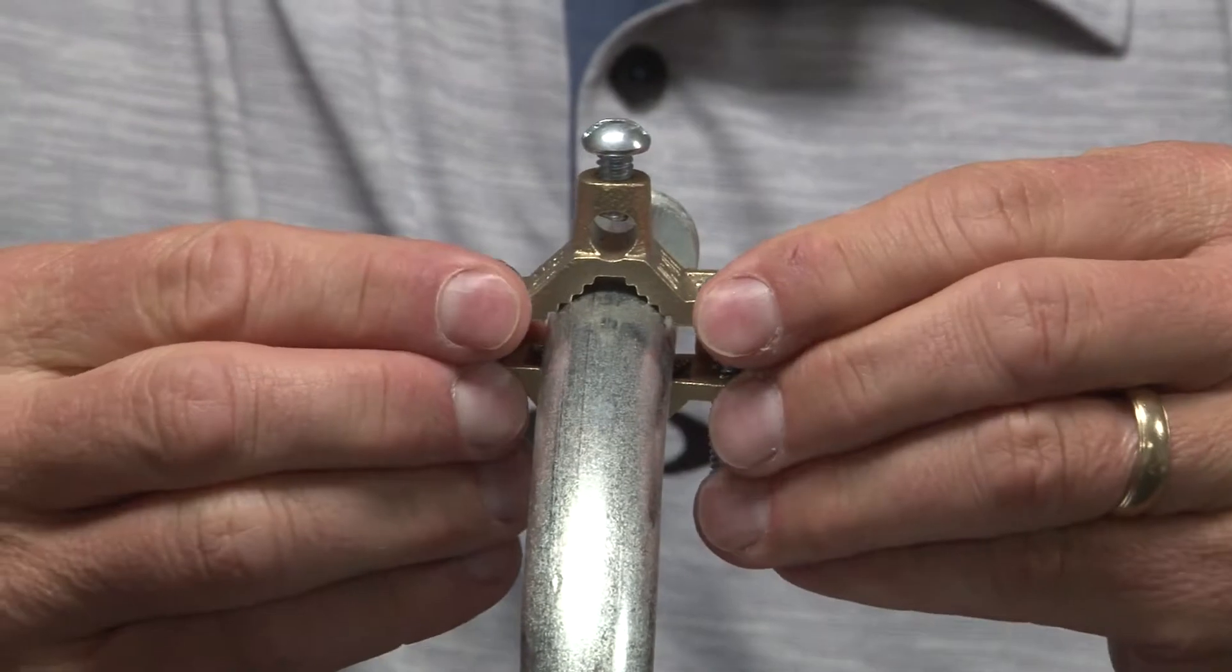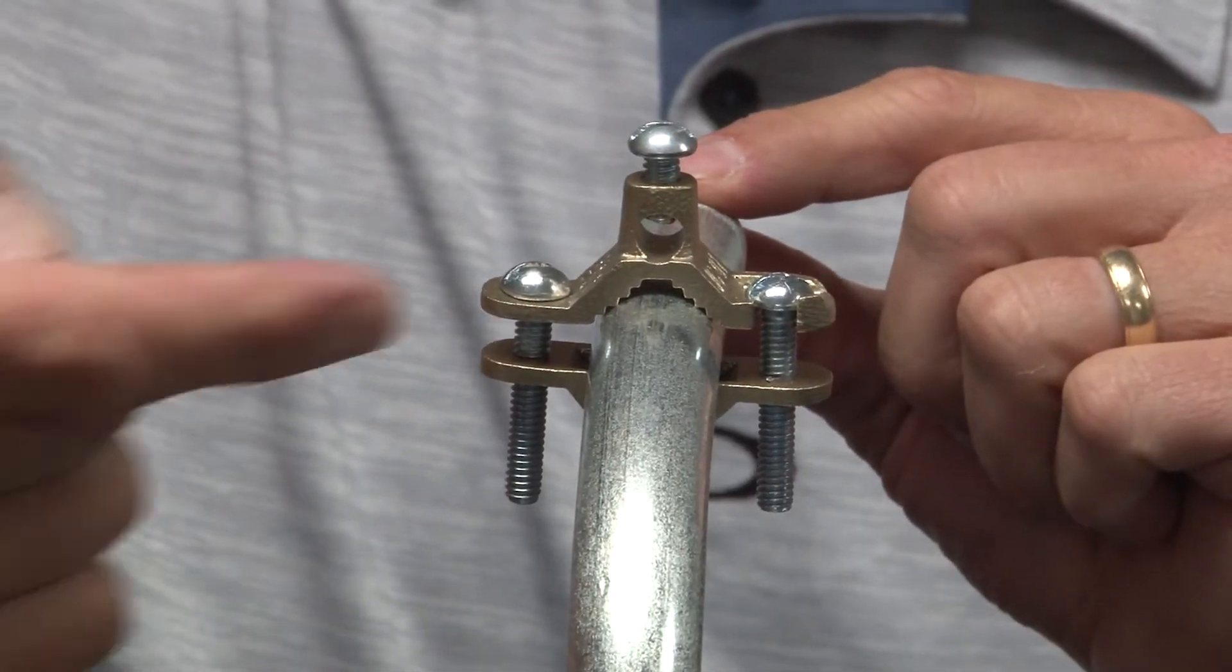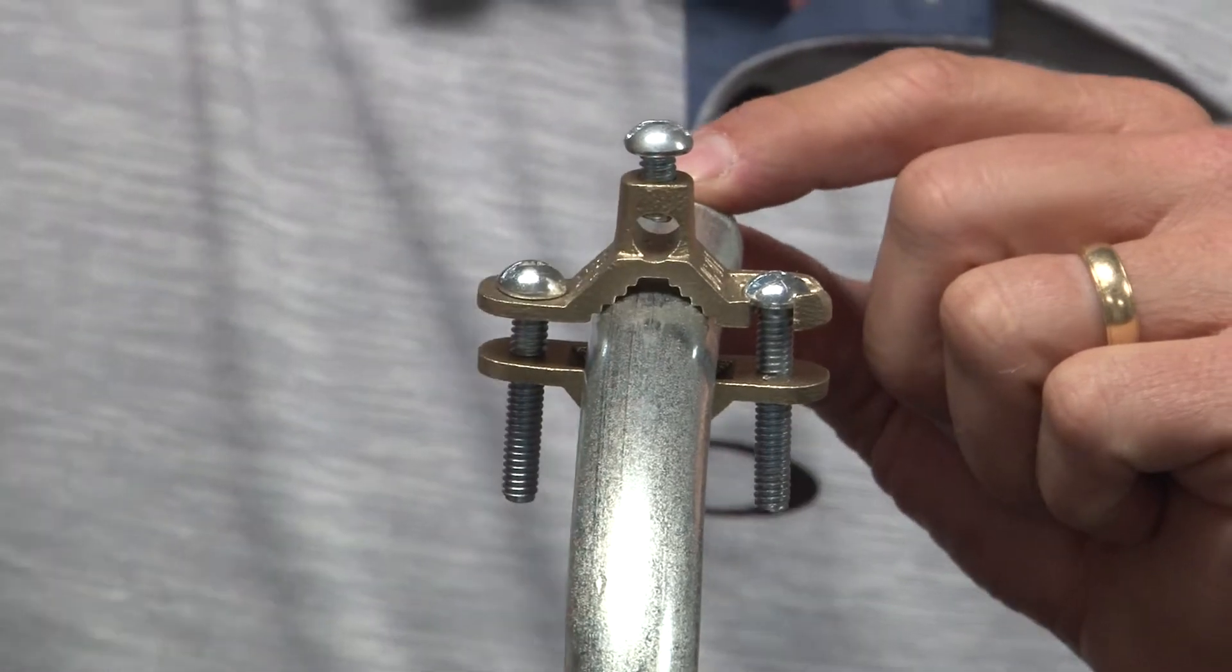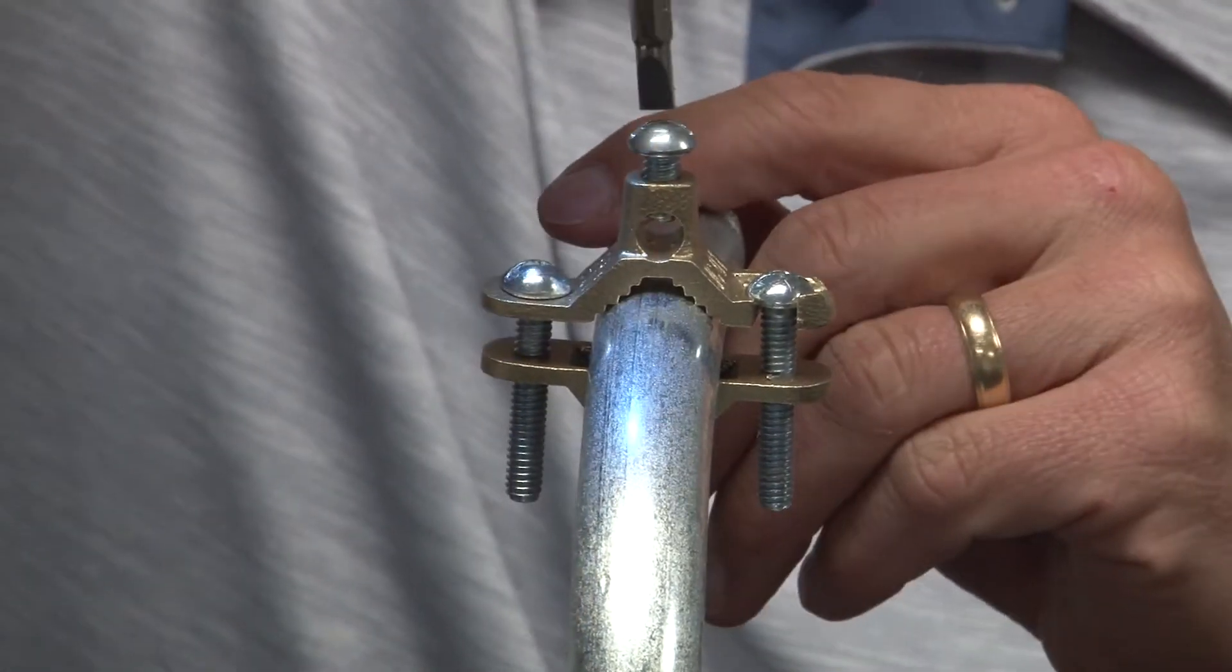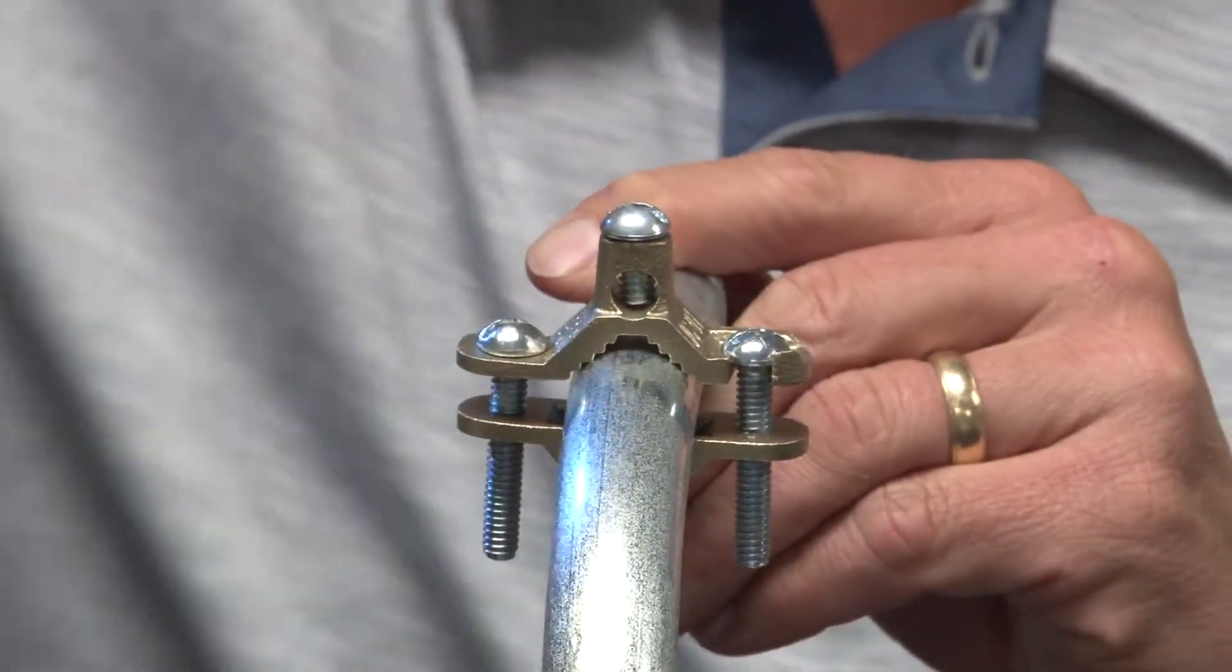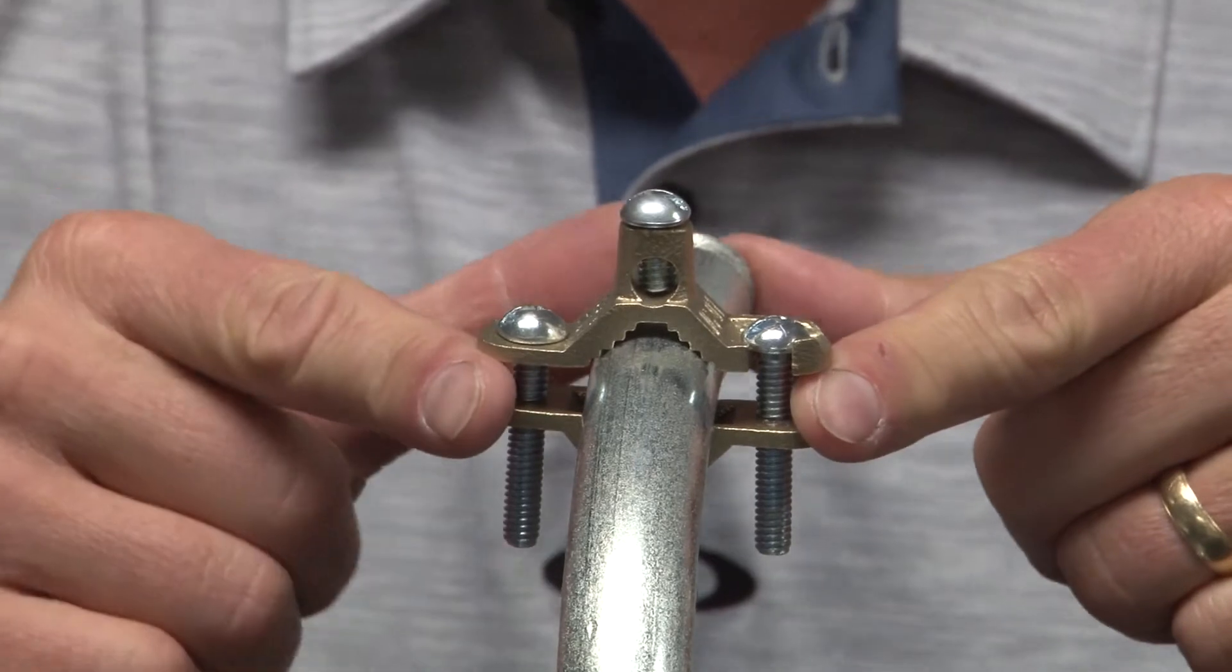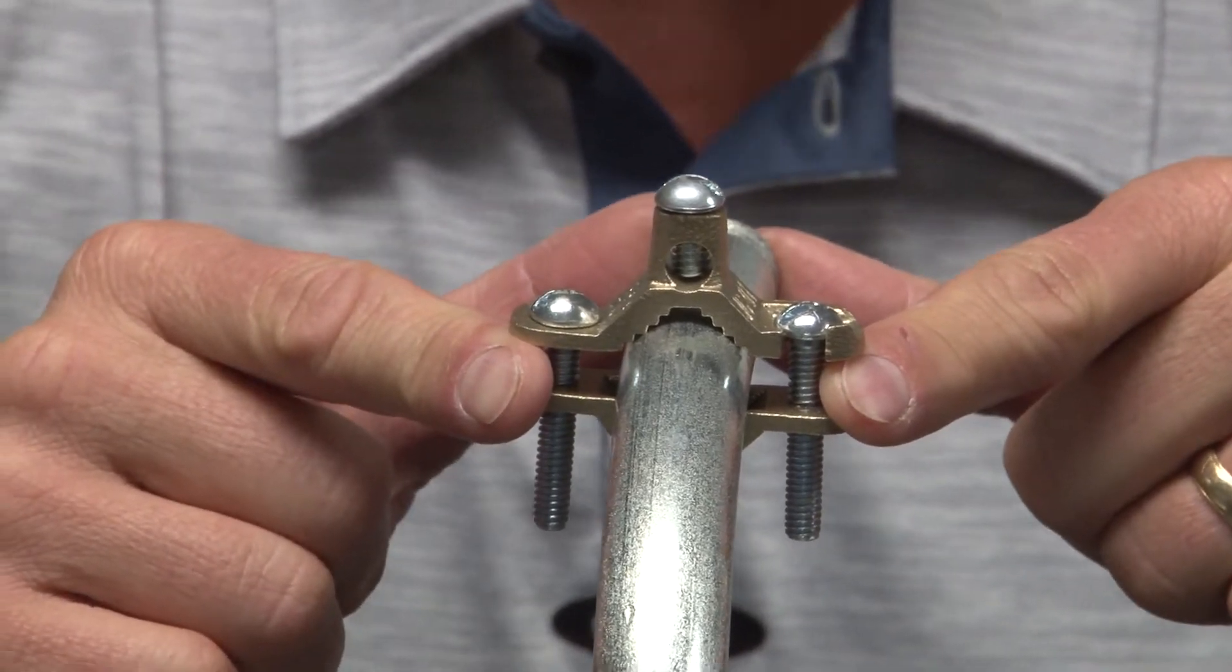Once you have a good tight bond with the clamp to the water pipe, you simply insert the ground wire through the top hole. As you'll see, the set screw bites against the ground wire, holds it in place, and ensures that you have a good bond for your electrical system to the earth.